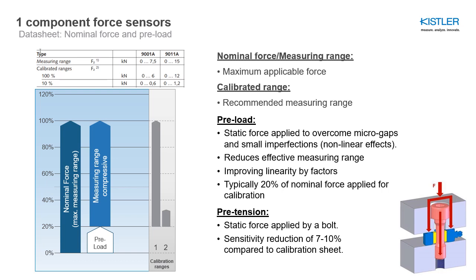Just a remark about preload and pretension. Preload is something different than a pretension, because at the preload you apply a force on the sensor, like putting a weight on it, and that leads to the force flux which goes completely through the quartz crystals within the sensor. A pretension, on the other side, is applied by a bolt, where you tighten the bolt and squeeze the sensor between a bottom and a top plate.